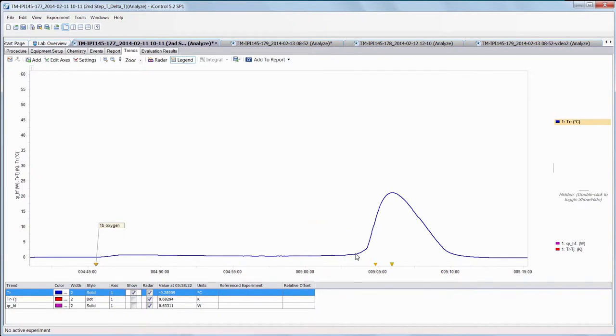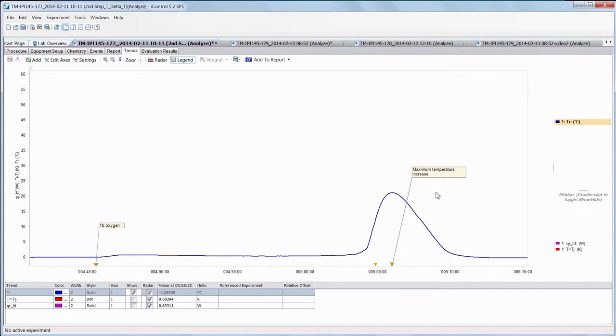And if you monitor temperature at a given time, which is about 15 minutes after the introduction of oxygen to the vessel, you have a strong temperature increase in the vessel. Unless you're not in front of the system, which may happen by the way, you're not going to miss that. It's a 20 degree increase, you're going to conclude it's a pretty exothermic reaction.